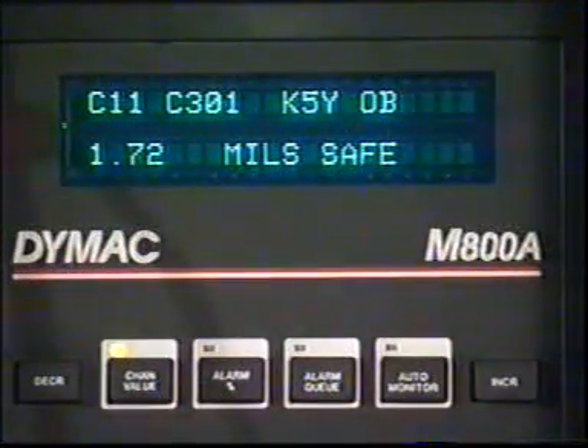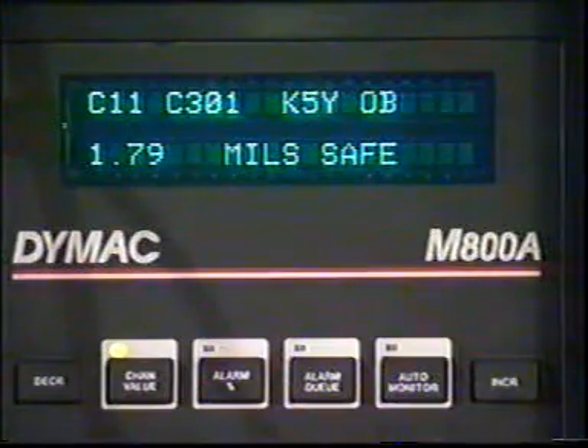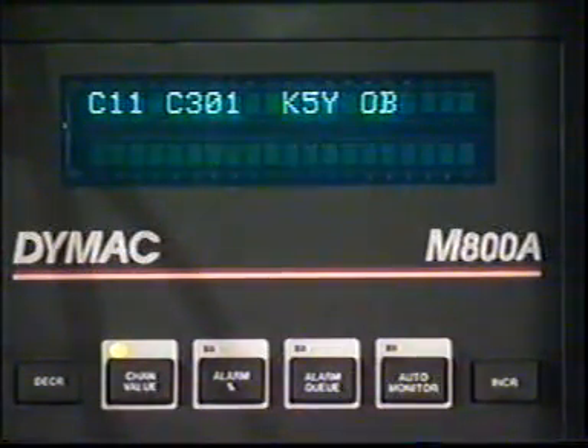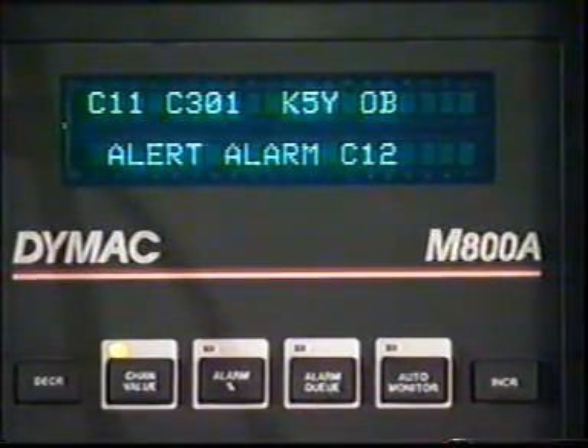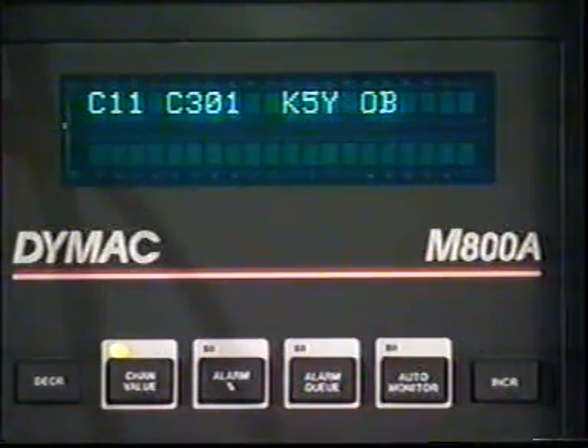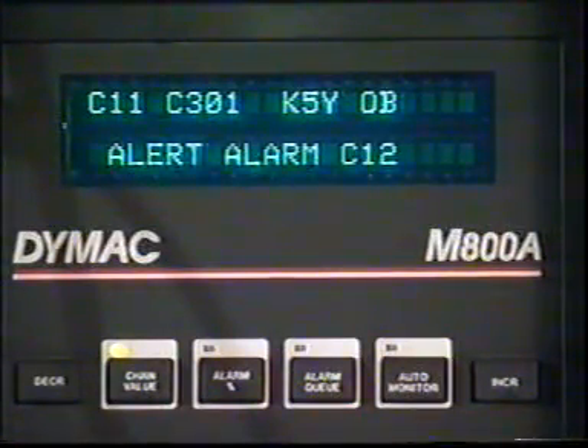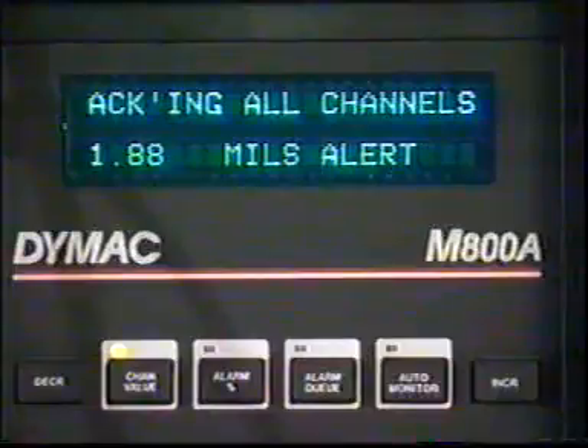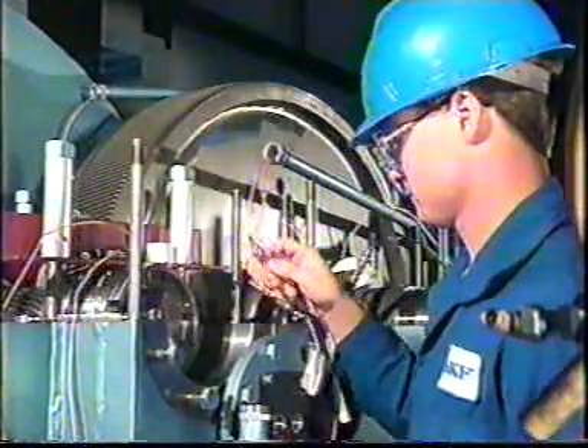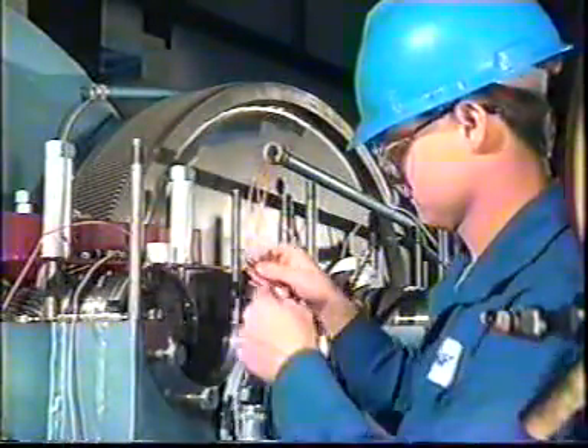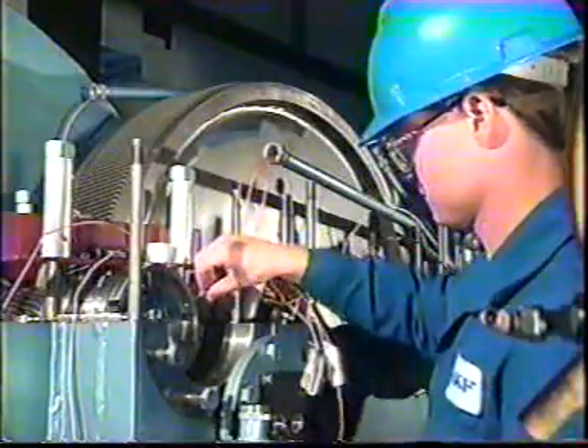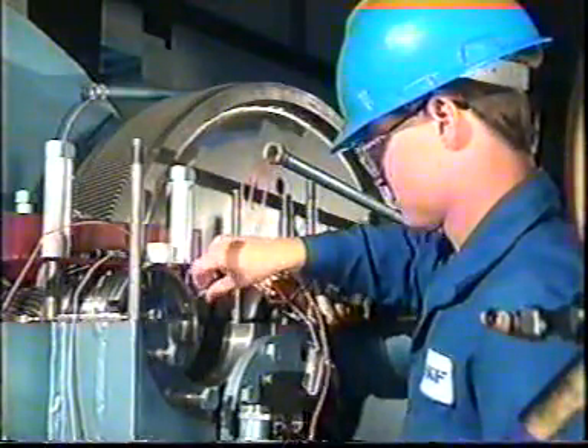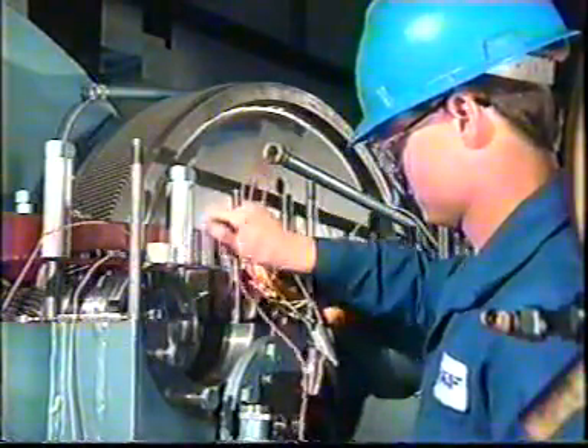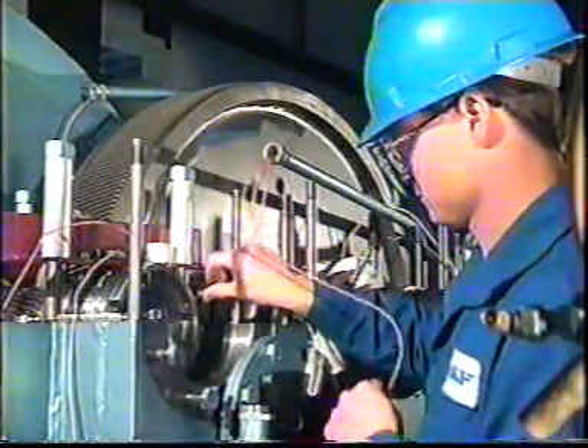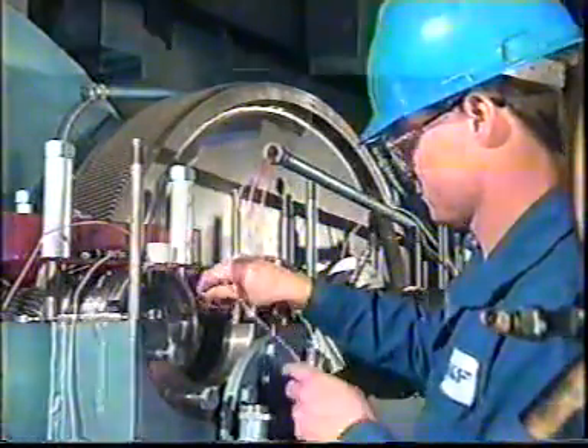While conducting monitor calibration, it's a good idea to check alarm set points. Most alarms are user-adjustable, and they should be checked periodically to ensure they provide the proper output at the proper input level. If a component needs replacement, be sure to follow your facility's guidelines for lockout-tagout, and make sure you have an exact replacement. Calibrate and check sensors before installation.